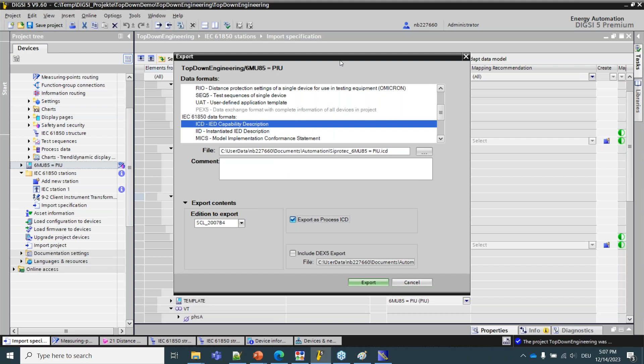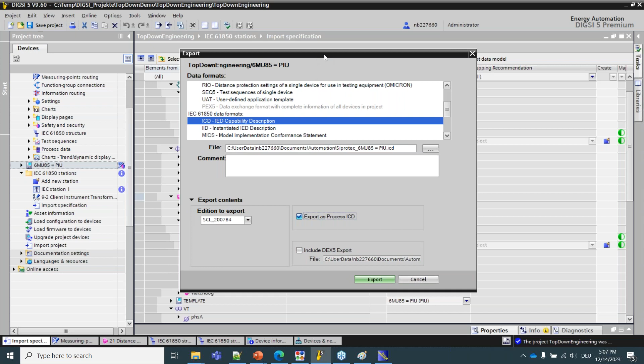Once that mapping is done for every signal, either the signal exists by default and it's just one-to-one mapping, or it's about creating the required functionalities and signals in the device, we can export the process ICD file with a new option containing the process ICDs that will inform what data are supported by the device, how the original name in our tool was by default, and how the signal is in the specification. We can do it that way to keep exactly the same names in our device by default, or if the purpose from the utility is to go towards a unified data model and more interchangeability, with no deviations at all, we have the possibility to import the data model changes into the device to take over all the logical devices, logical node prefixes and suffixes into our data model.